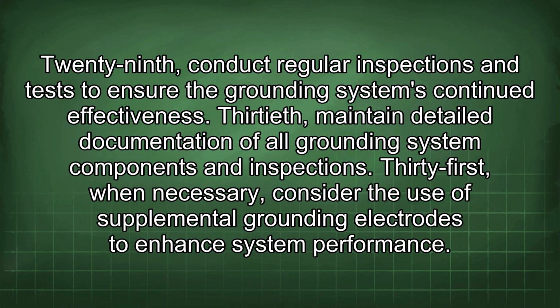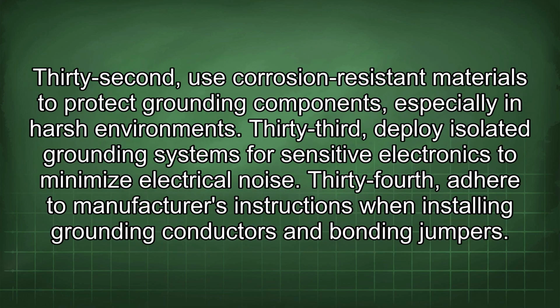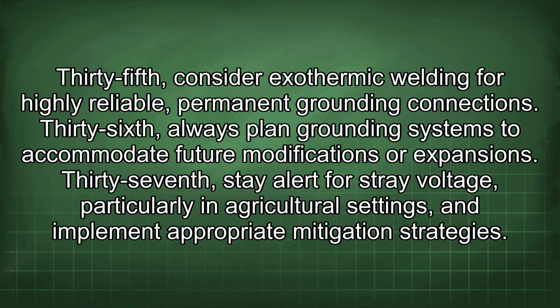31st, when necessary, consider the use of supplemental grounding electrodes to enhance system performance. 32nd, use corrosion-resistant materials to protect grounding components, especially in harsh environments. 33rd, deploy isolated grounding systems for sensitive electronics to minimize electrical noise. 34th, adhere to manufacturer's instructions when installing grounding conductors and bonding jumpers. 35th, consider exothermic welding for highly reliable, permanent grounding connections.